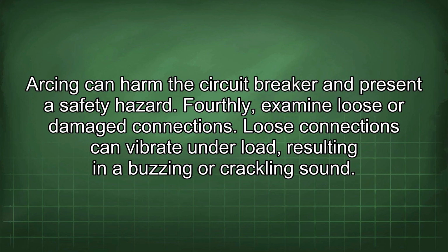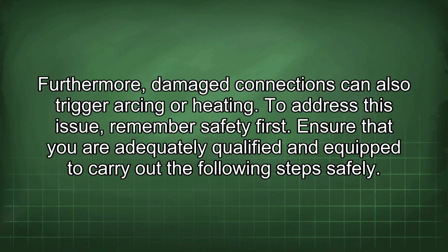Fourthly, examine loose or damaged connections. Loose connections can vibrate under load, resulting in a buzzing or crackling sound. Furthermore, damaged connections can also trigger arcing or heating. To address this issue, remember safety first. Ensure that you are adequately qualified and equipped to carry out the following steps safely.